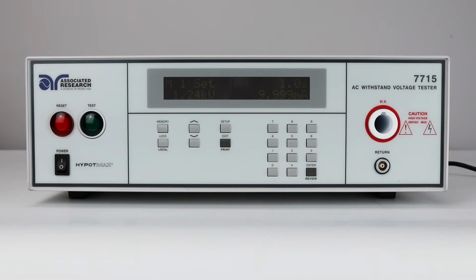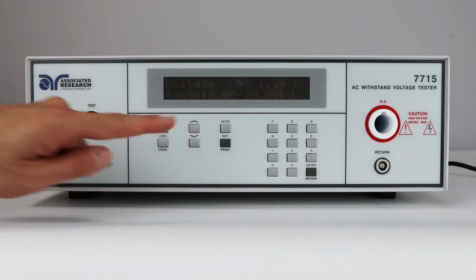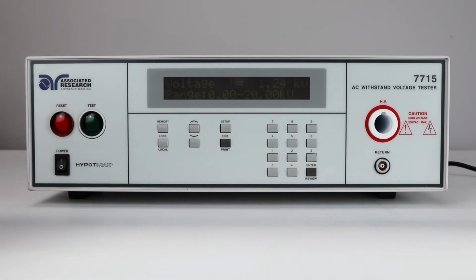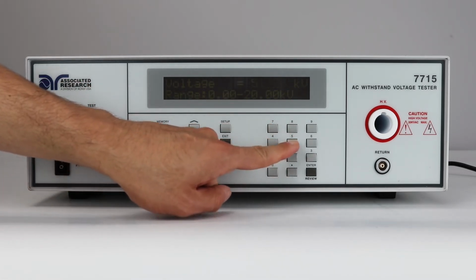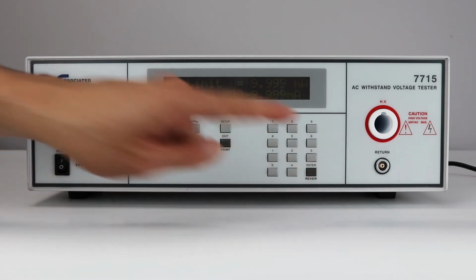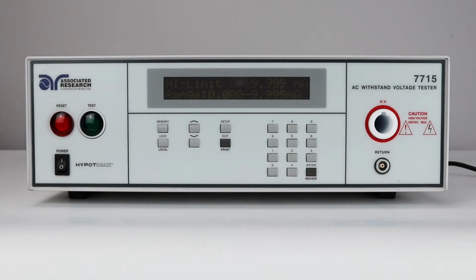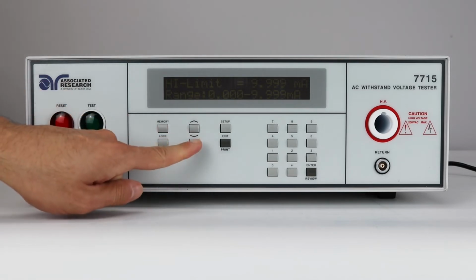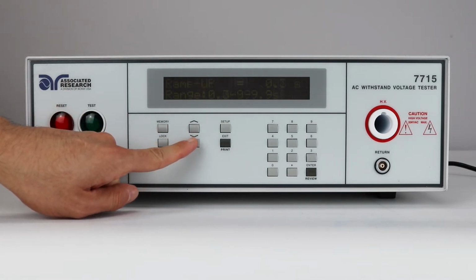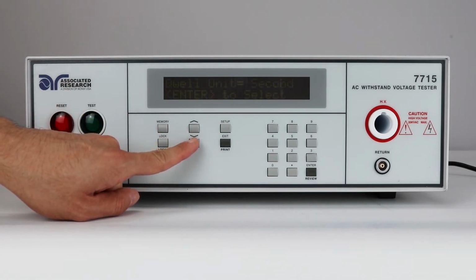The HypotMAX series instruments have a total of 50 memories. Next, we will need to set up the parameters to the AC Hypot test. To edit the parameters, simply press the up and down arrow key to navigate through the test parameters. If entering a numeric value such as voltage, use the numeric keypad to input a value.